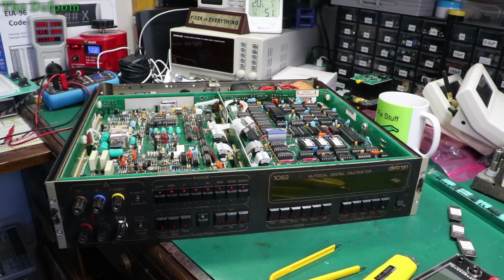It measures that voltage, which should be about 1 volt, and then compares that using the A to D converter against the stored value for that particular test, and it's got to be within 6%. If it's outside 6%, then it will give a self-test failure. So I think I need to check that 10k range and see what's going on there, or maybe there's an issue with that particular resistor or something.